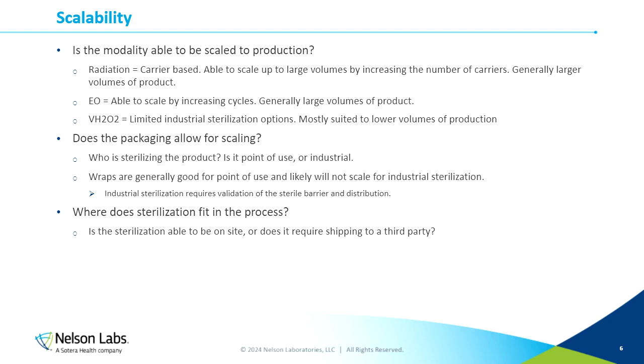So that leads us into implementing your hydrogen peroxide. And one of the considerations with that is your scalability. So is the modality able to be scaled to your production? As some examples of industrial sterilization, we have radiation sterilization, and it's carrier based. So your product is sent to an industrial irradiator. It's loaded onto a carrier. So it's offloaded off your pallets onto a carrier, and you're generally able to scale your product in production to just include more and more carriers. So it's able to be scaled very reasonably and very quickly. But that also means that it's set up for larger volumes of product. If you make a single box of product, an entire carrier may not be the most cost-effective approach.